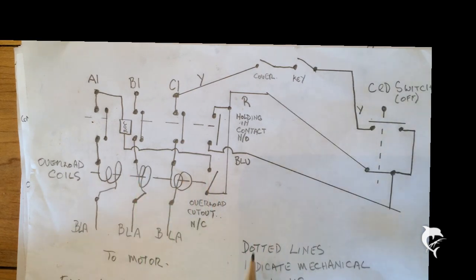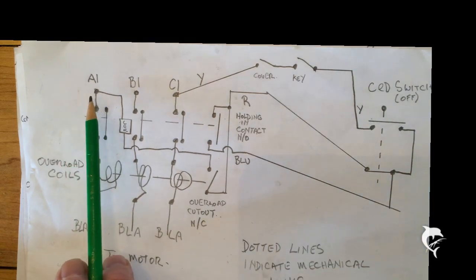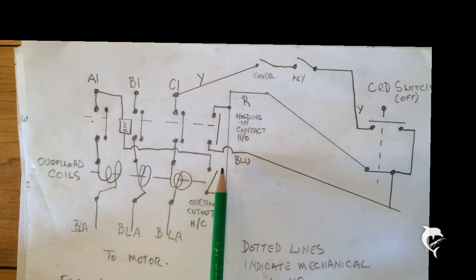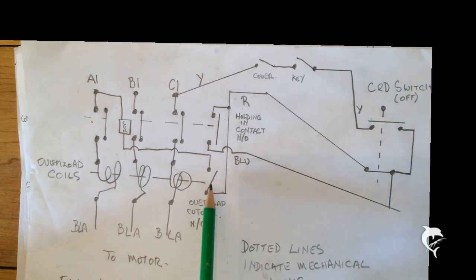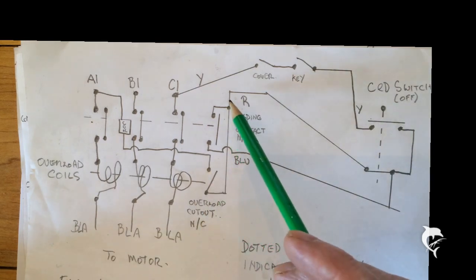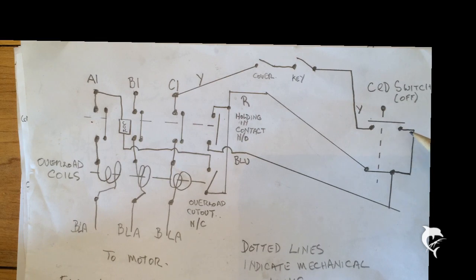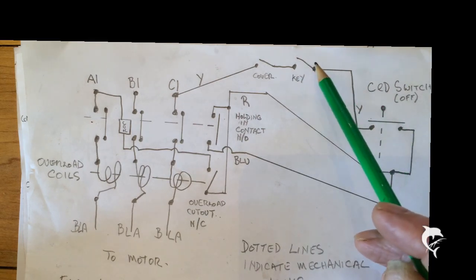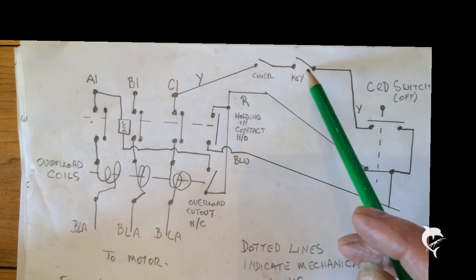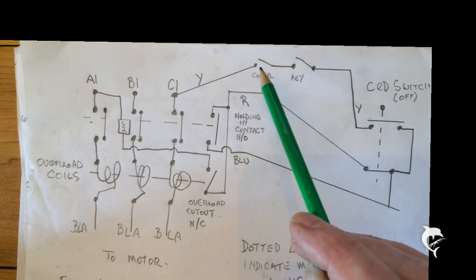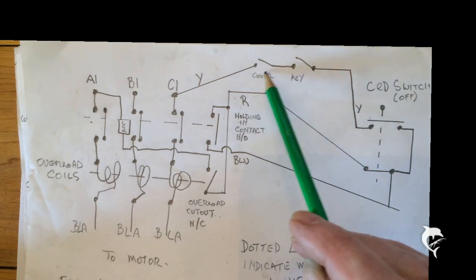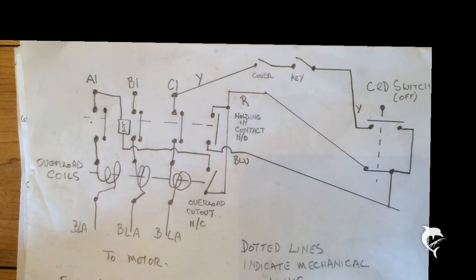So you can think your way through the circuit by starting at A1, which is a line in, going through the coil, through the overload cutout switch which is labelled here normally closed. I've drawn it in the open position, but at rest when it's reset it's normally closed. And then we go up there through the on-off switch, and then back through the safety circuit, which is the key switch which locks the drawers and switches the lathe on and off, and also the cover switch which prevents the lathe being operated without the end cover on, back to another phase.